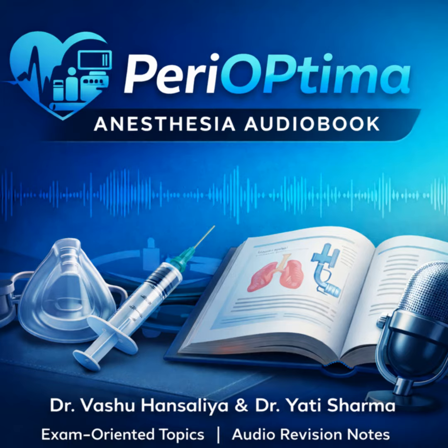But in severe aortic regurgitation, a lot of it comes right back. A huge chunk of it flows backward into the ventricle during diastole. And the forward flow is often turbulent. The device just sees this massive change in impedance and calculates an enormous stroke volume. But the effective forward flow, the blood that's actually perfusing the body, is much lower. Exactly. So it will drastically overestimate the true cardiac output. The clinical pearl here is simple. If the patient has a known significant leaky valve, do not trust the bioimpedance monitor for an absolute number. It might still trend, but the number itself is likely wrong.